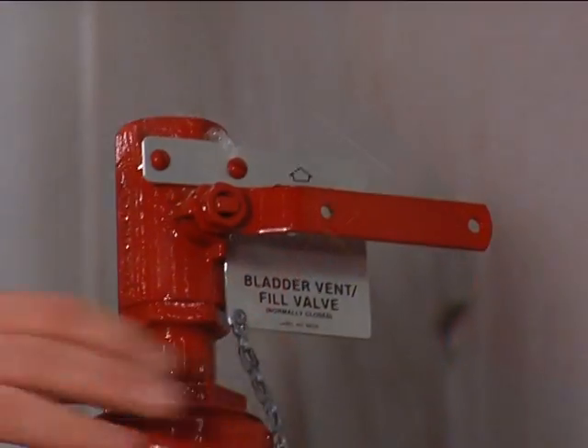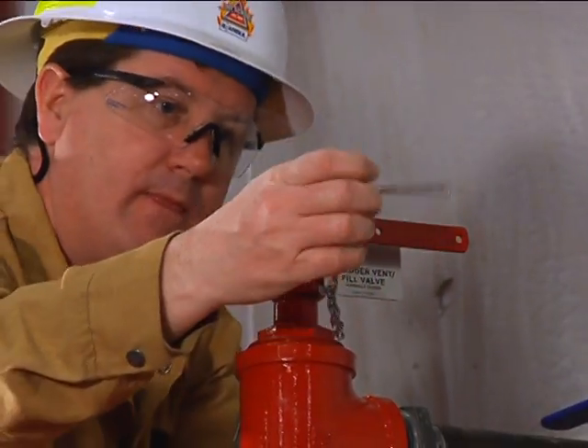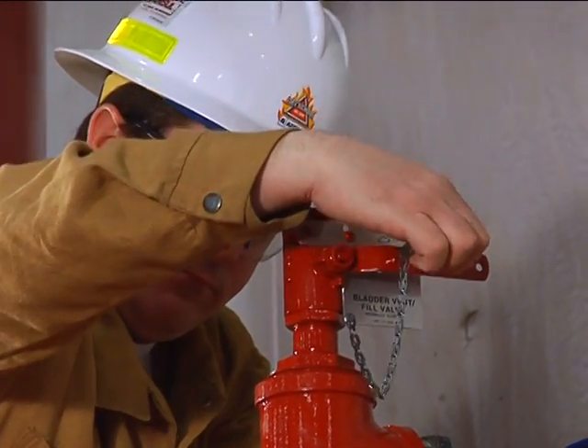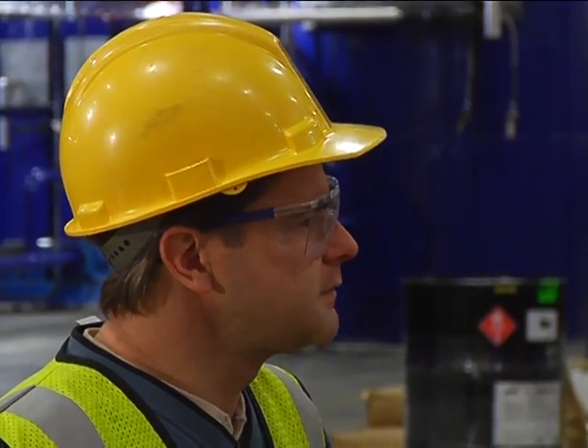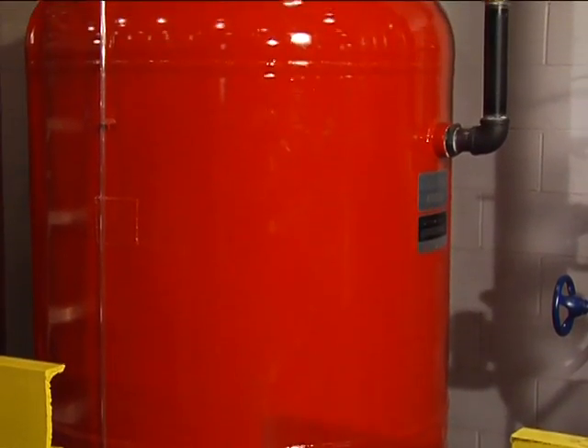Next, insert the ring pins through the valve handles into the brackets and install visual inspection seals. Finally, record the date of the minor refill and notify any operating personnel that the system is back in service. Now you have successfully completed a minor or partial refill of Ansul's bladder tank.